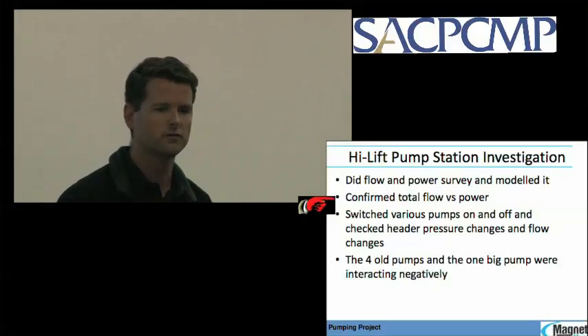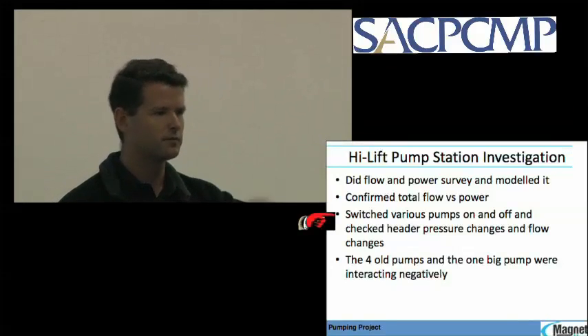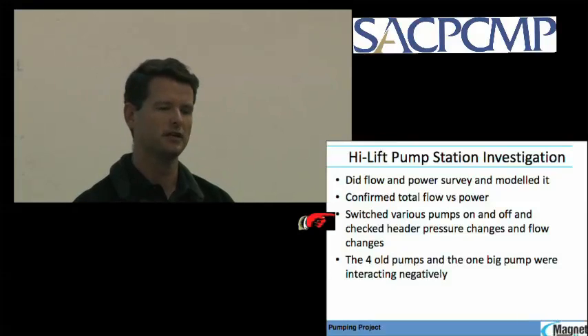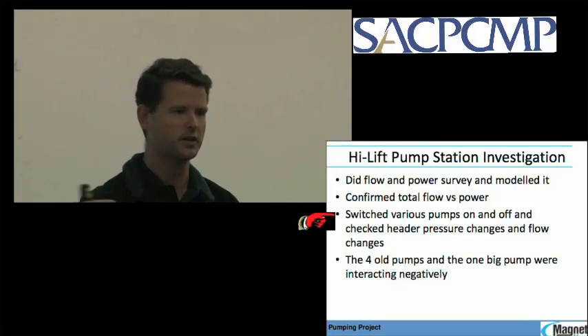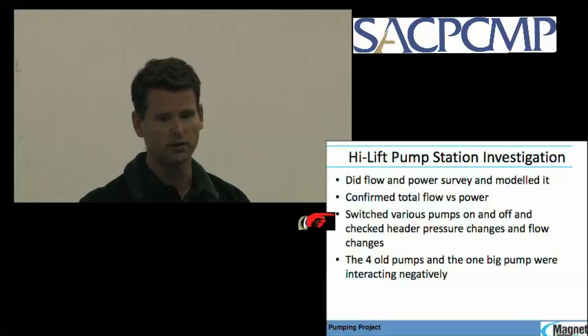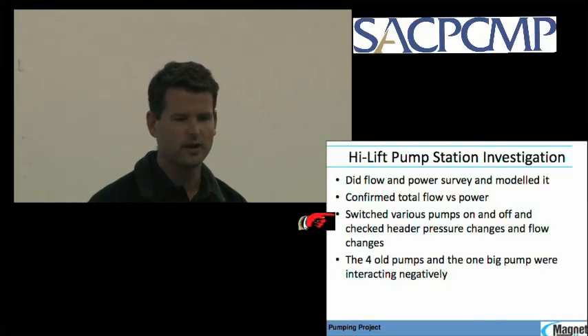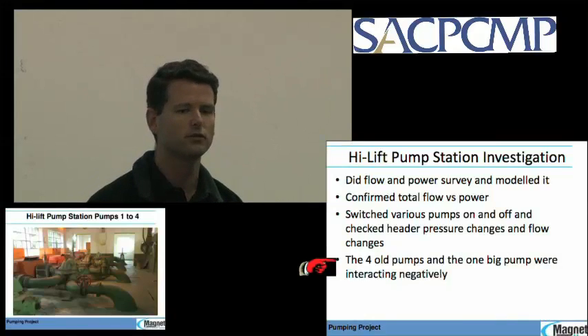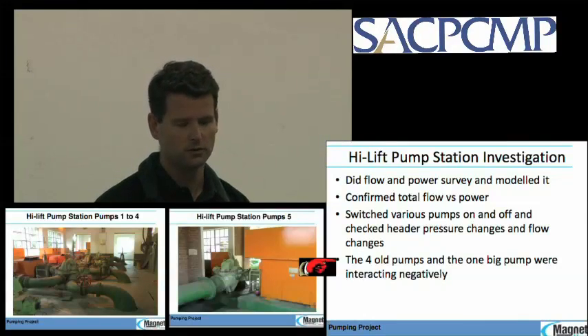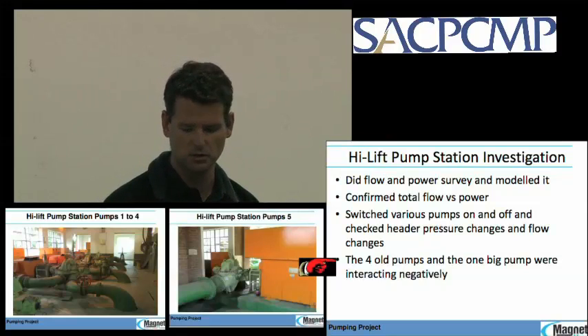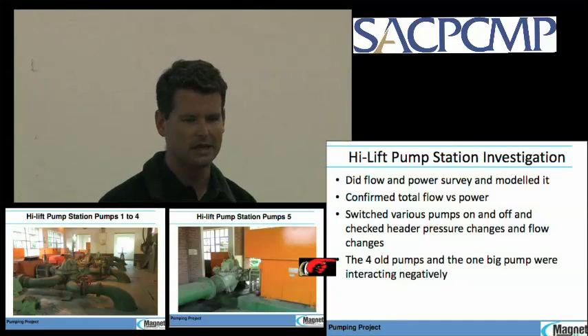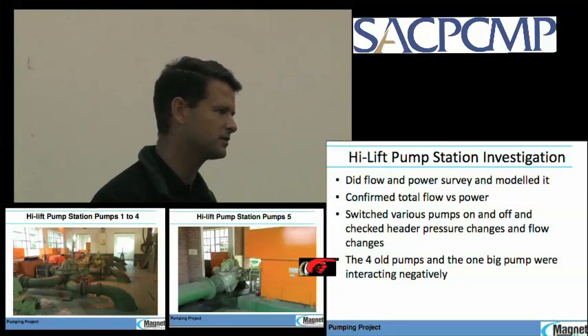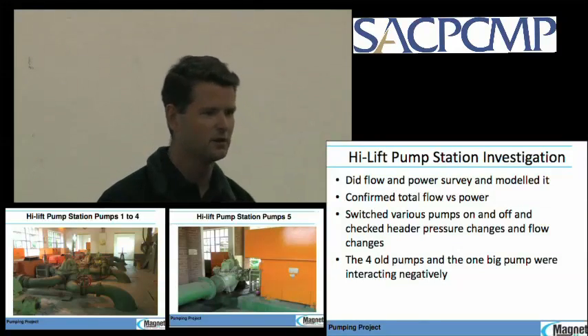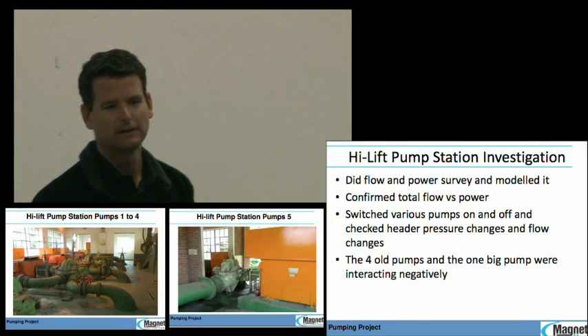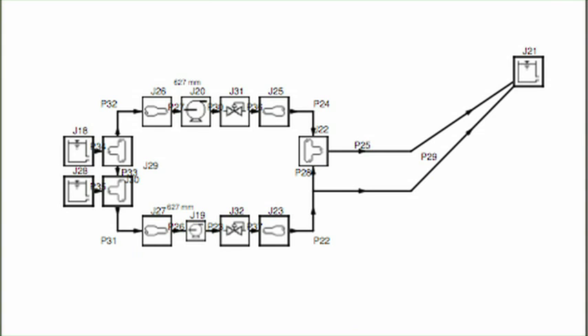So we confirmed the total flow versus power. We switched various pumps off and watched how the flow changed. And then typically in any parallel situation, every time you switch on an extra pump, you get less and less gain for a whole lot of extra power. And not surprisingly, the 4 old pumps were interacting negatively with the one big pump to a dramatic extent. And in fact, the last pump that they were switching on was doing something, but very little. And of course, those old pumps had different sized impellers in, and were throttled on the discharge to different extents, because if they didn't throttle it, it would trip. So this was what we finally went for.